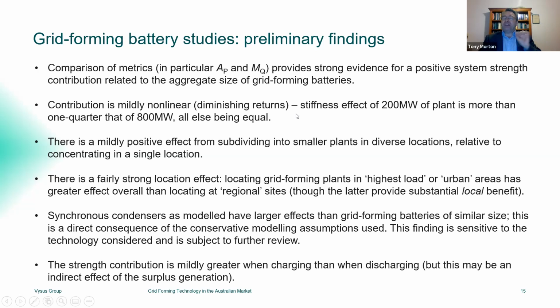That's the first dot point. But the second dot point says that we do see a non-linearity in that contribution. If we look at the strength contribution of a 200 megawatt grid forming plant compared to an 800 megawatt plant, the 800 megawatt plant doesn't actually give us quite 4 times the strength contribution. So there's a little bit of a law of diminishing returns: the first 200 megawatts you put in has the biggest contribution. The next 200 megawatts has a slightly smaller contribution. It still makes a big contribution, but we see that contribution get just a little bit less as we increase the size at the one location.